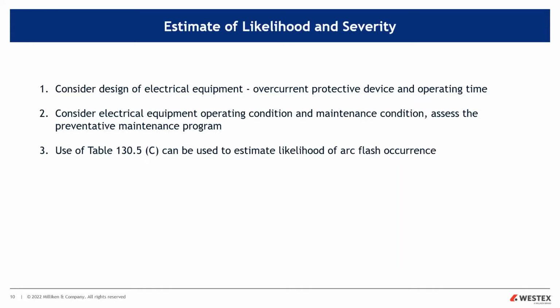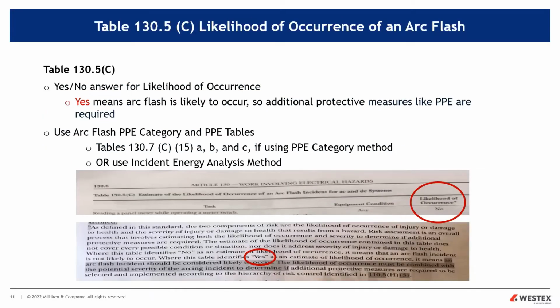Now, if help is needed, or if you're using the PPE category method, i.e. the tables and the standard, you can utilize Table 130.5(C). And I have the heading here, if you can see the top there, it's basically the first table you consult if you're doing the PPE category method. And you see here it has the task that you're doing, then it has the equipment condition. It's either in any, or it might be normal, or maybe abnormal, and then it's going to have likelihood of occurrence. Now, if it says no, you don't have to take any additional protective measures. But if it says yes, a yes means that an arc flash is likely to occur. It's not that it might occur or could occur, that it's likely to occur. So you need to take a look at additional protective measures, and we'll talk about that in a second. And that's the first, of course, table you look at, and there's two others that we'll look at here in a little bit if you're using the PPE category method.